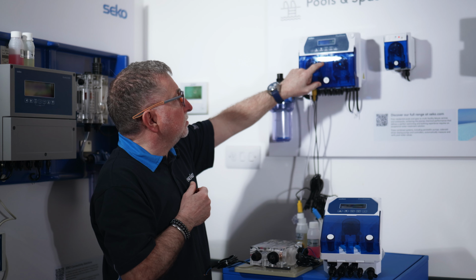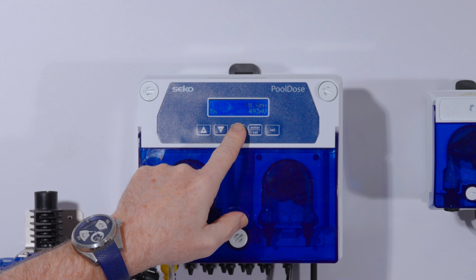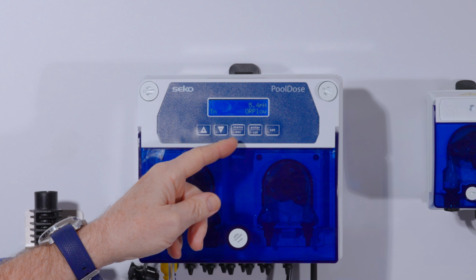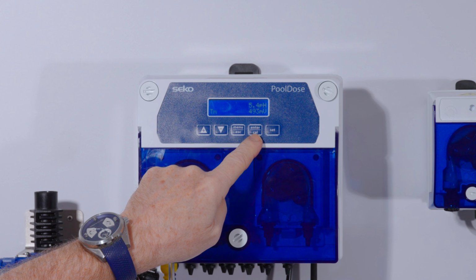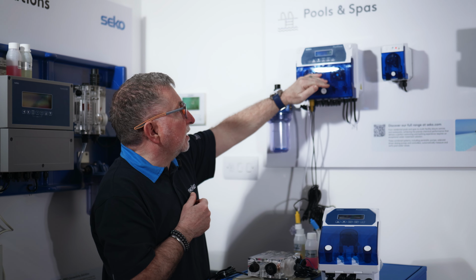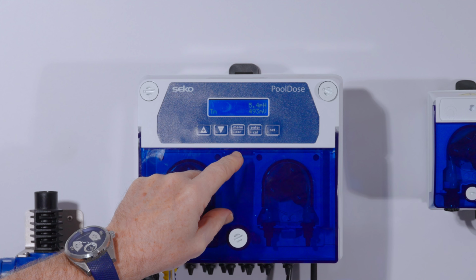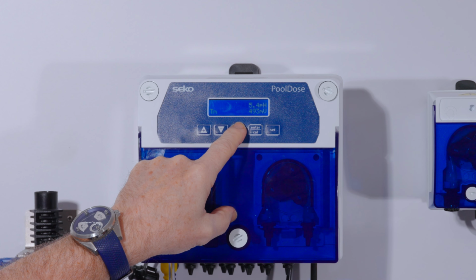As you can see, we have 5 buttons on the display of the PoolDose Double, an up and down button which is used to scroll through the menus, a menu button which is used to enter or escape from the menu, a calibration button and a set button. The set button is to view the set points, and you can change those without having to actually go into the menu.